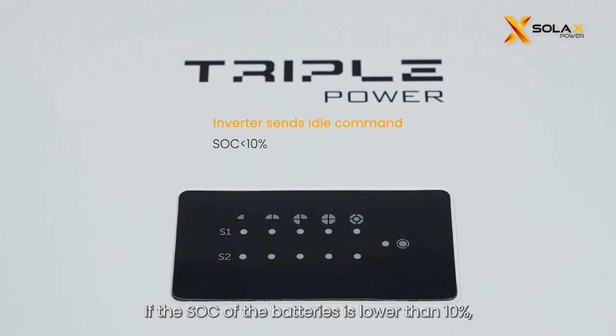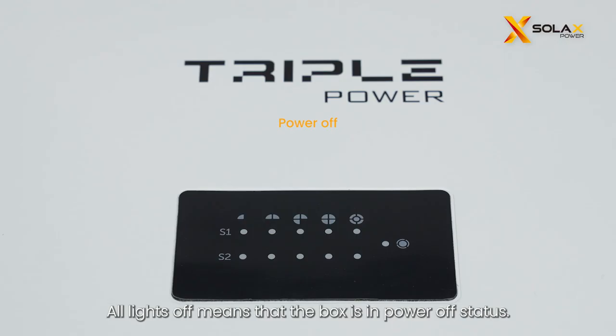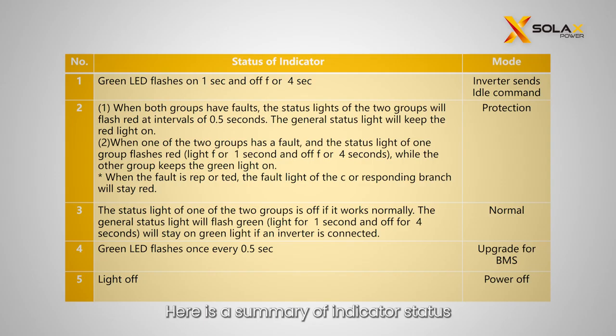If the SOC of the batteries is lower than 10%, the inverter would send an idle command to the box, and the general light will flash in green. But when the cell voltage is lower than 2.7 volts, all lights will go out. All lights off means that the box is in power off status. Here is a summary of indicator status and the corresponding meanings.